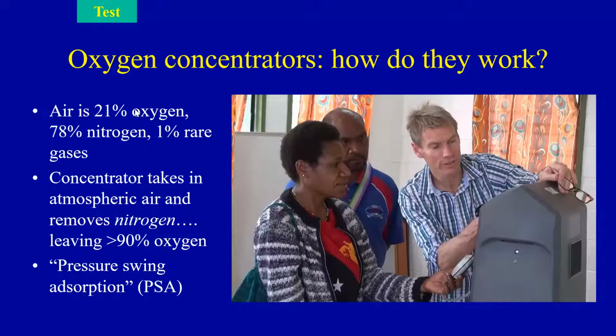So I know you know that the air we breathe is 21% oxygen, 78% nitrogen - so most of the air we breathe is nitrogen - and then 1% just rare gases like argon. A concentrator takes atmospheric air, entrains it into the back of the concentrator, and then removes the nitrogen. That's what it does, it removes this 78% nitrogen. So it concentrates up oxygen, it makes more pure oxygen, if you like. And what you get is more than 90% oxygen.